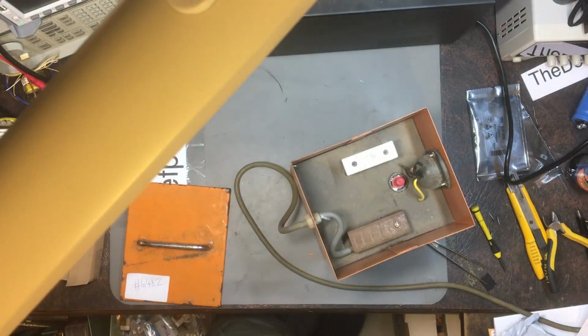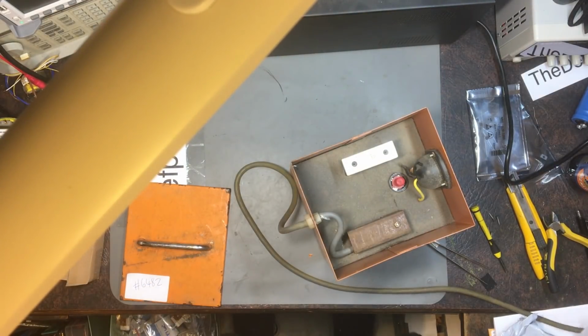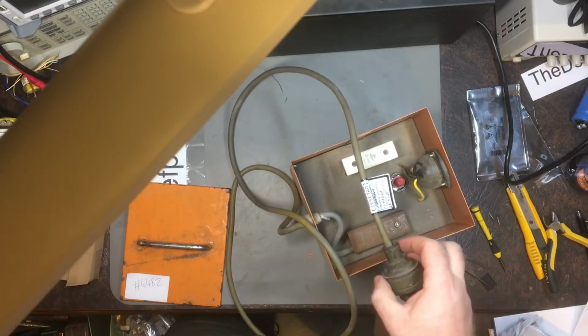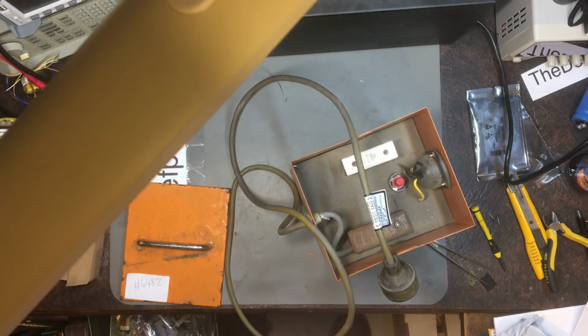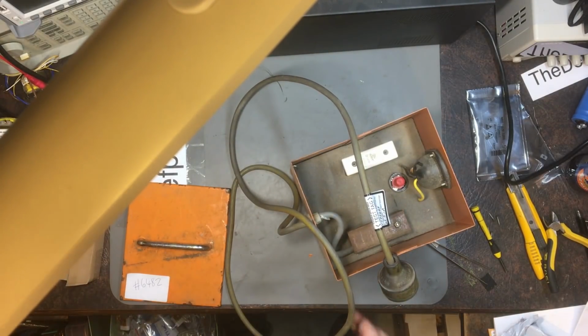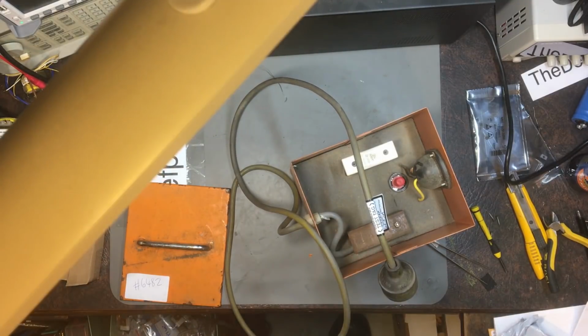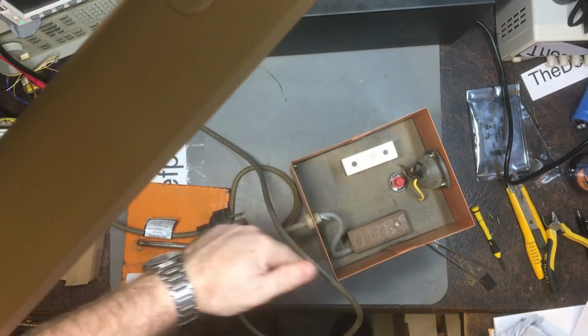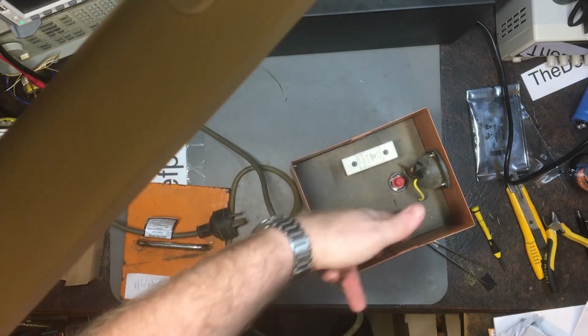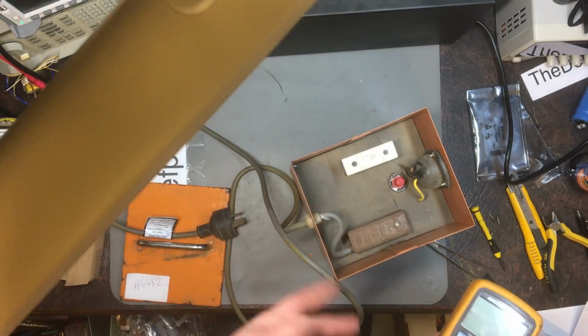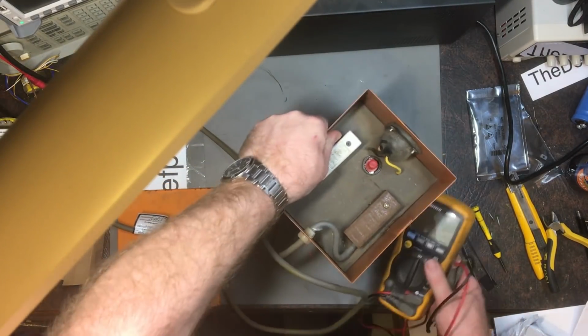And we shall do some basic checks. Let me get my old Digitech out and do a couple of basic checks on it. There's no earth connection on the casing, but that's alright - it's an isolation transformer. It has an earth pin on the plug, but there's no earth tag on the casing anywhere to attach an earth. So it's probably fine.